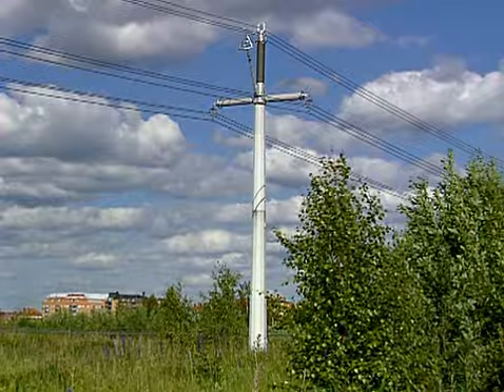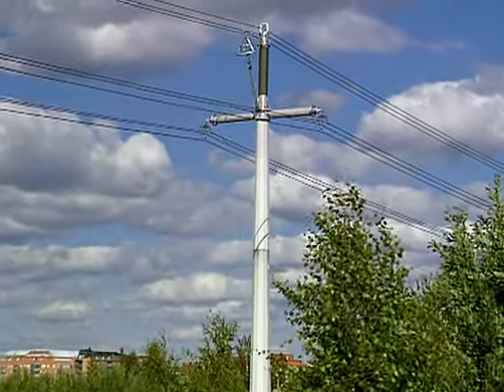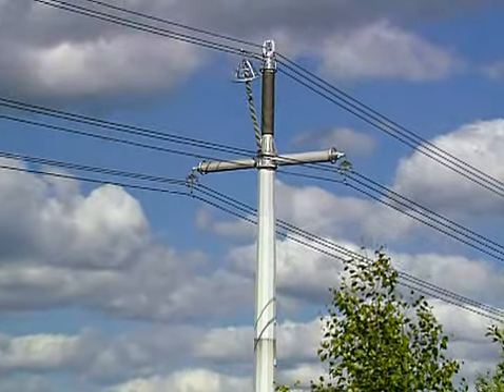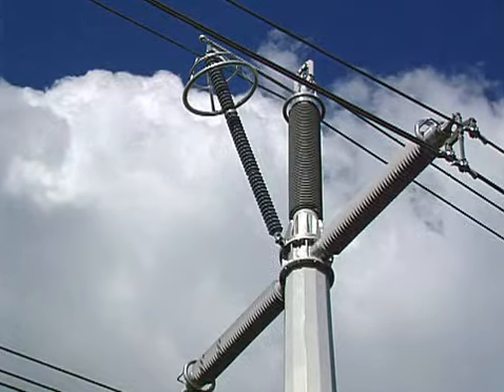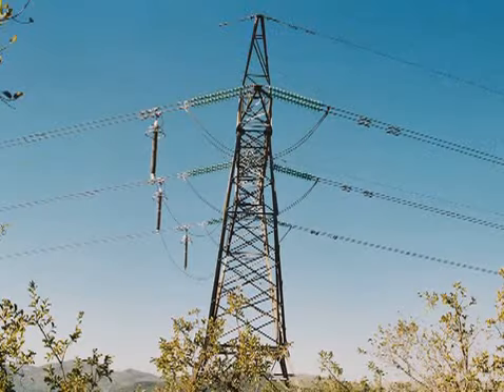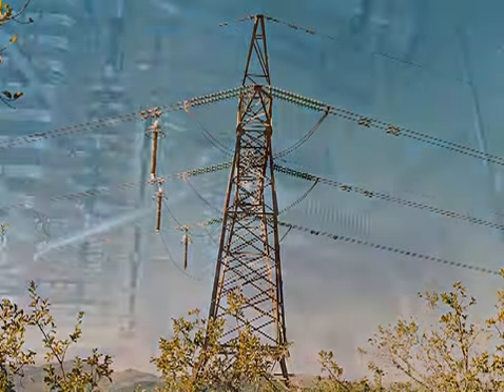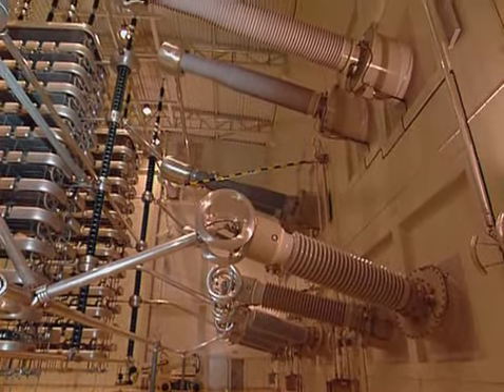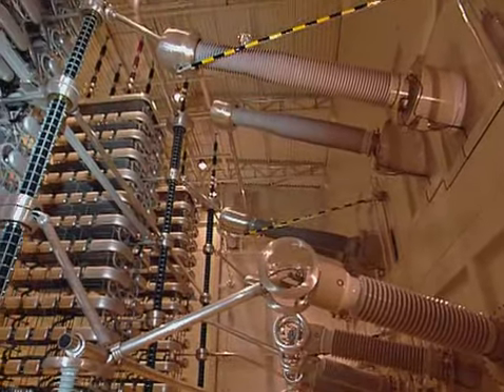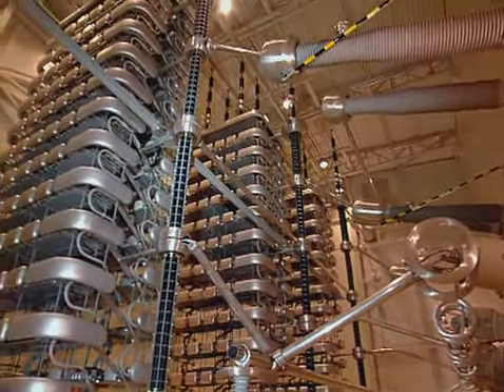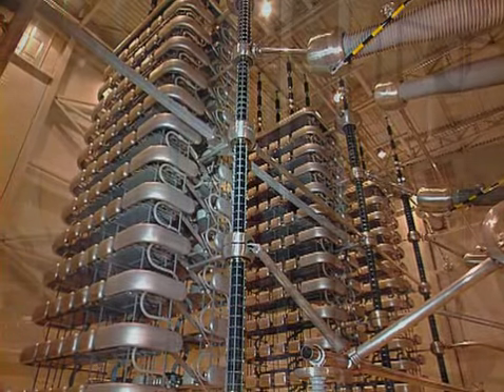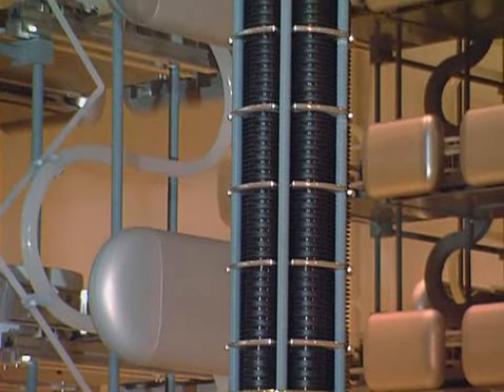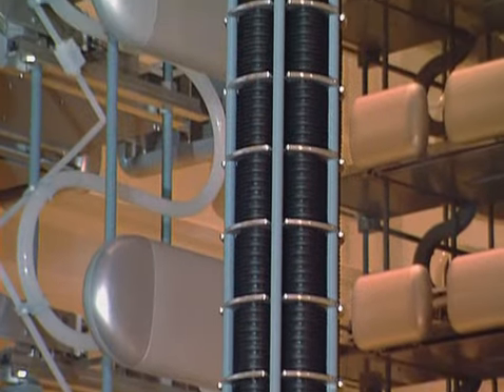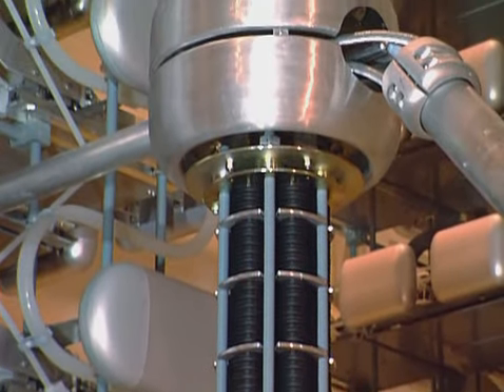PEX Link is a perfect design for compact insulation lines. Placing PEX Link in the top phase of a compact 400 kilovolt line eliminates the need for the traditional overhead shield wire. ABB has applied PEX Link for system voltages up to 800 kilovolts. An entirely different application for surge arresters is the tailor-made variant for HVDC facilities, in which the arrestor keeps the overvoltages to a minimum. This allows you to choose a lower insulation level for the components, thereby reducing costs.